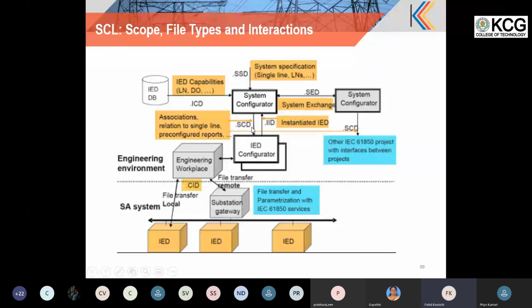So SSD and ICD are combined to form an SCD file, the substation configuration description, and this is downloaded to the specific IEDs through the IED vendor tool. This is the configuration mechanism described in 61850. First I do the substation specification, then take the real data through the ICD files, construct everything, every feeder, every transformer, everything linked, and make an SCD file. The corresponding IED vendor tool is provided with the SCD file, and for the corresponding vendor IED you can download the relevant part from the SCD file to the IEDs, and the specific file will be named the configured IED description, nothing but the CID file.